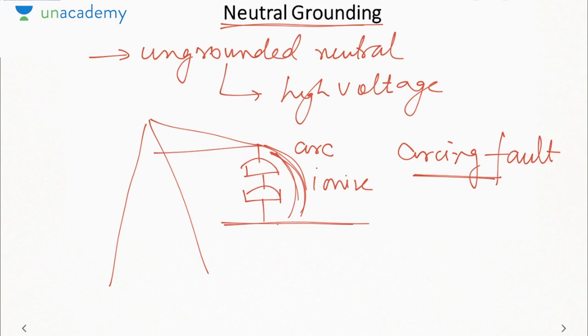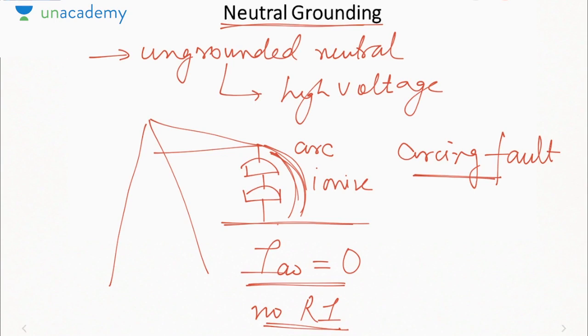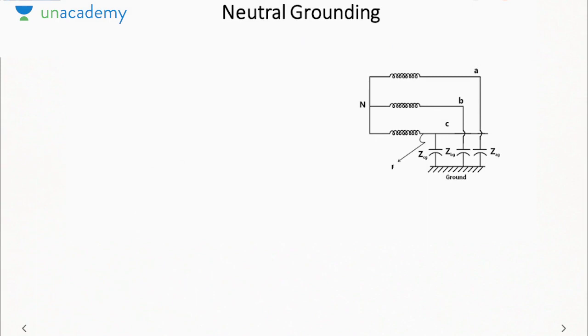The only advantage of isolated neutral is that the equivalent circuit that we saw was open circuited, so zero sequence current will be 0. If Zn is infinity, Ia0 will always be 0. So no radio interference, because as I told you, in an unbalanced system the radio interference is only due to the zero sequence current, and hence there will be no radio interference. But the danger is the formation of an arc due to isolated neutral. The other danger is due to the high line charging current.